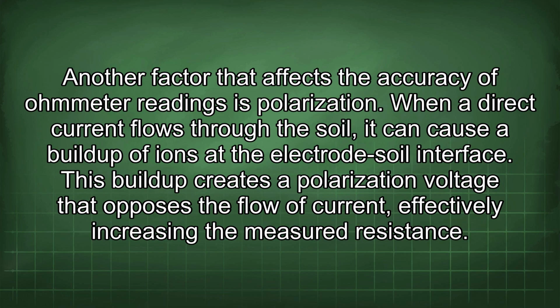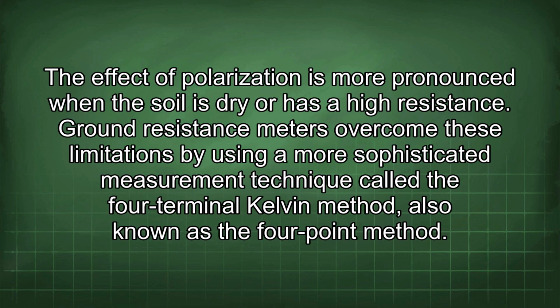Another factor that affects the accuracy of ohmmeter readings is polarization. When a direct current flows through the soil, it can cause a buildup of ions at the electrode-soil interface. This buildup creates a polarization voltage that opposes the flow of current, effectively increasing the measured resistance. The effect of polarization is more pronounced when the soil is dry or has a high resistance.